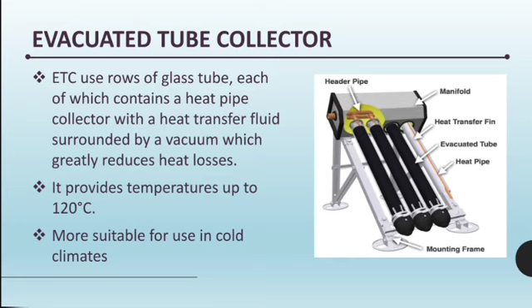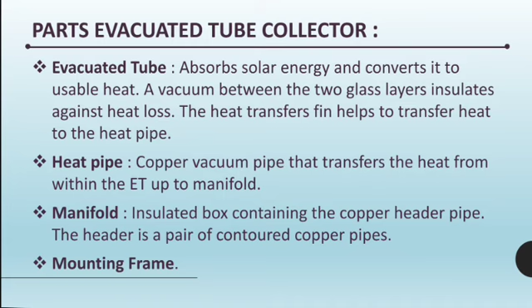Evacuated tube absorbs solar energy and converts it to usable heat. A vacuum between the two glass layers insulates against heat loss. The heat transfer fin helps to transfer heat to the heat pipe. Heat pipe. Copper vacuum pipe that transfers the heat from within the evacuated tube up to the manifold. Manifold. The insulated box containing the copper header pipe. The header is a pair of contoured copper pipes. Mounting frame. Working of evacuated tube collector.